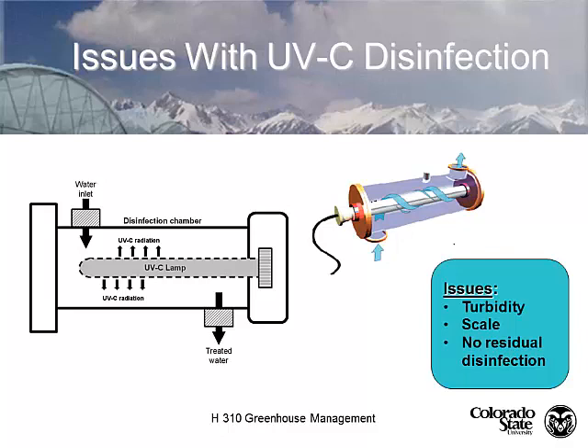Issues with UVC radiation: if the water has any debris reducing clarity, we need longer contact time or higher intensity. Water scale buildup on the lamp itself is a problem. Importantly, UVC does not provide residual disinfectant — when the water leaves the lamp, it's disinfected, but once it leaves, if there's an opportunity for contamination, it can be easily recontaminated. On the other hand, the lack of residual chemistry in the system is also a benefit since we're not adding any chemistry.